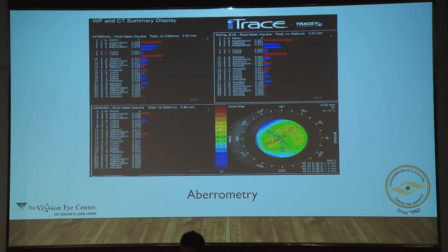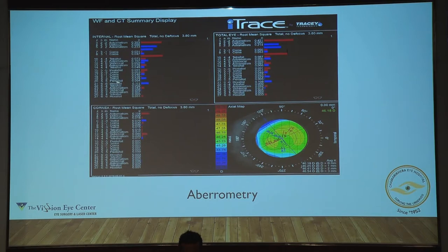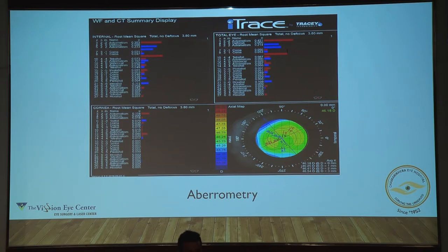This is the aberrometry of the iTrace — the iTrace is the latest tool on the block. The advantage it gives you is that it separately tells you the internal aberrations and separately tells you what the aberrations are on the cornea, so you know where the aberrations are coming from. It then adds them up and gives you a total aberration as well. There is no machine other than the iTrace right now in the market that can actually do that.